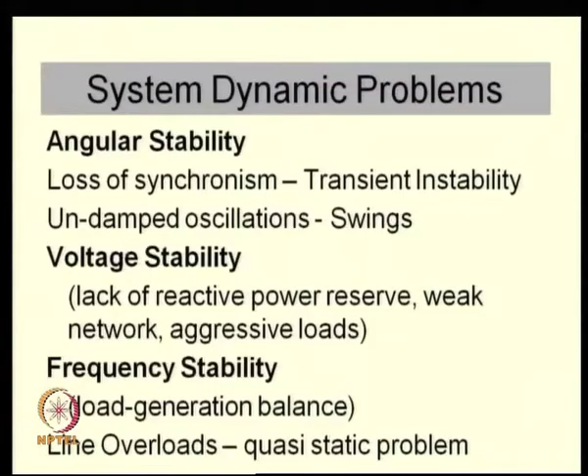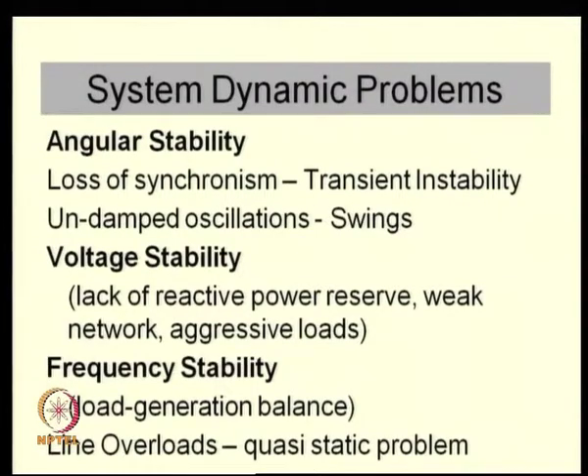Angular instability essentially consists of two phenomena: loss of synchronism, which is a large disturbance phenomenon also called transient instability; and undamped oscillations or power swings due to small disturbances. The damping of power swings can be improved by making changes in controllers — augmenting or having auxiliary controllers for controllable elements in the power system, like the excitation system in a generator or HVDC power flow control — to ensure that these swings are actually stable.